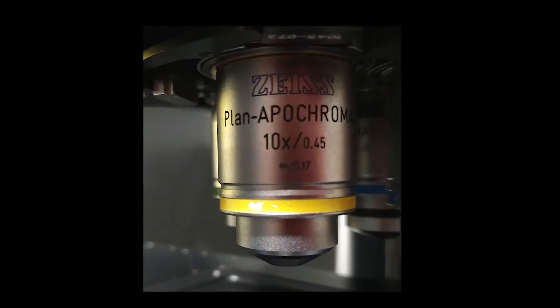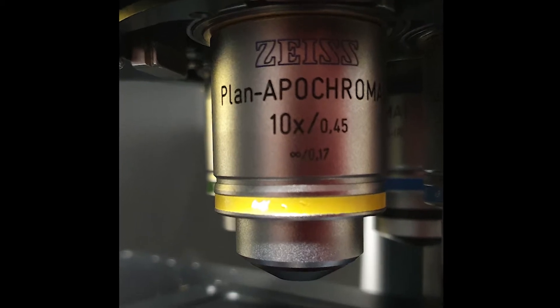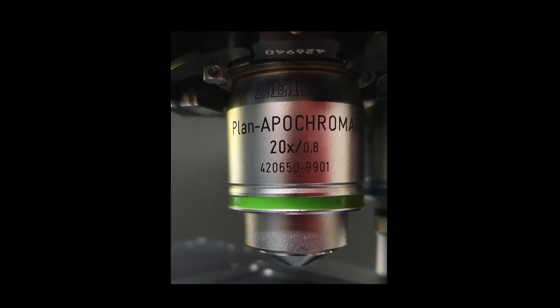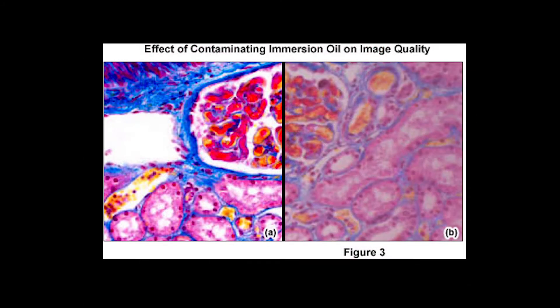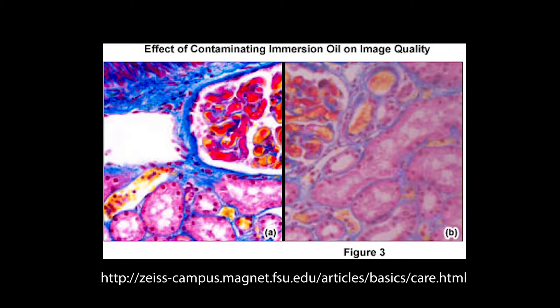Low magnification objectives such as 4x, 10x, and 20x are generally dry objectives that allow you to easily scan across the sample because they allow a big field of view and thicker optical sections. You do not want to get any oil on these objectives as it will affect your ability to obtain an image.